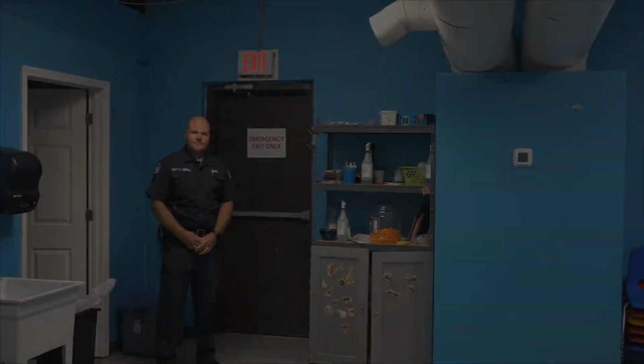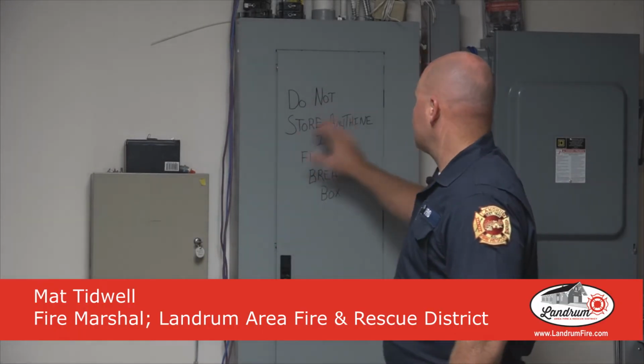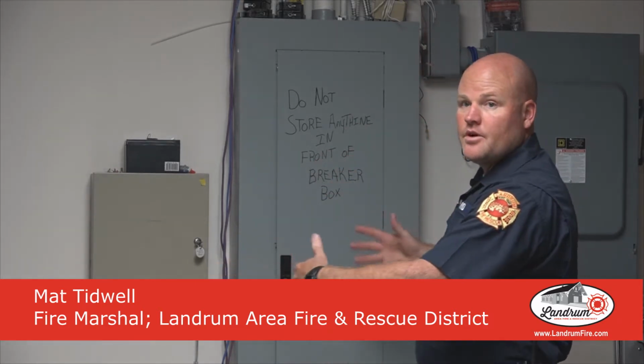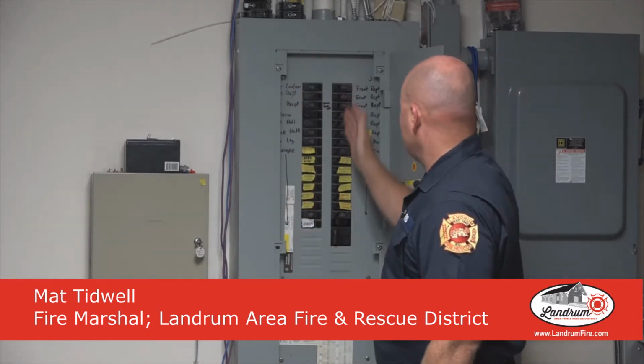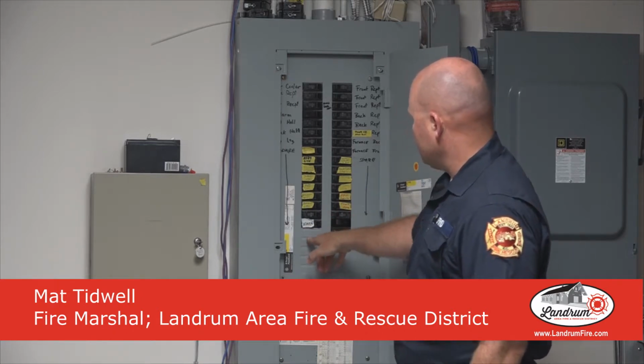All right, checking the electrical panel box. Love the sign, do not store anything in front of breaker box. By code, you've got 36 inches around it to make everything accessible. We're looking to make sure everything's in line, it's on, it's operating, and we're looking for covers. Everything's covered, so you cannot stick your finger through here.